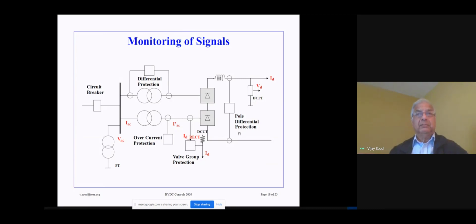For any pole differential protection, we can monitor the currents so that we can have some kind of differential protection added in. The DC current is monitored. The AC current rectified, which is coming in from the AC side, is also monitored. So these currents over here, these are three-phase currents. These are monitored. We rectify those in here and then convert that to a DC signal. The DC CT also measures the DC current. So these two can be compared, and you can give an indication to the valve group protection system.